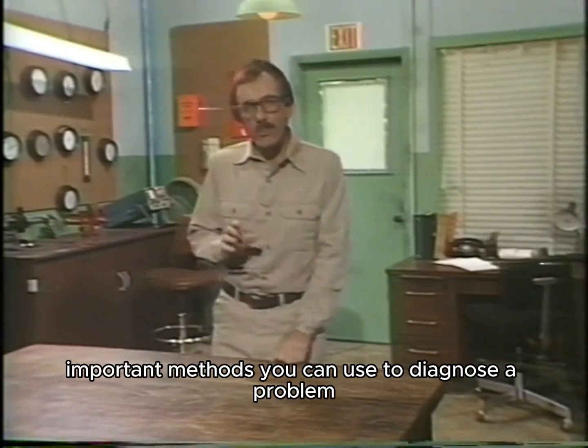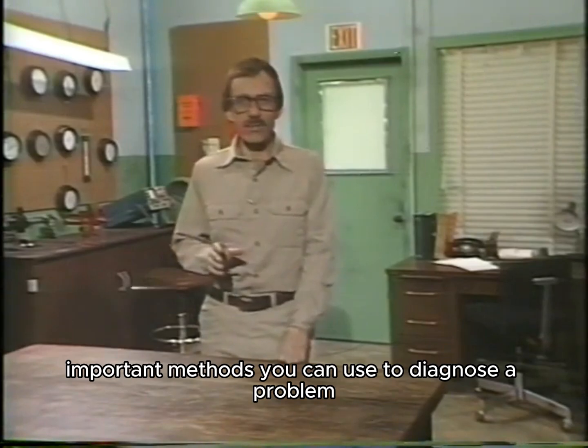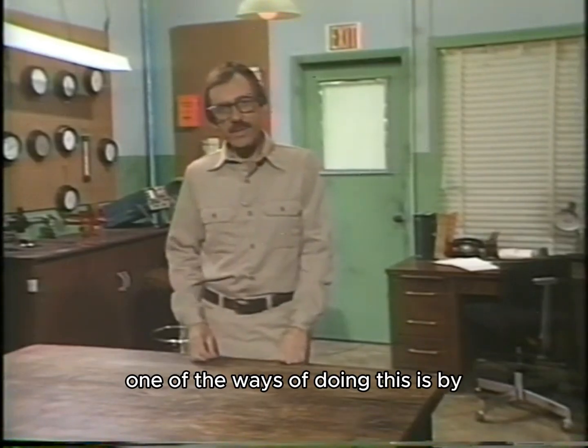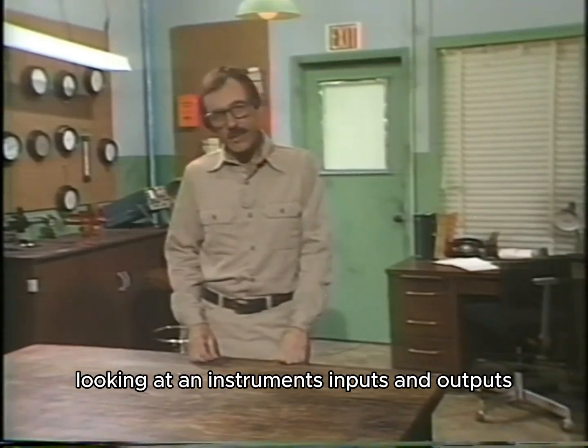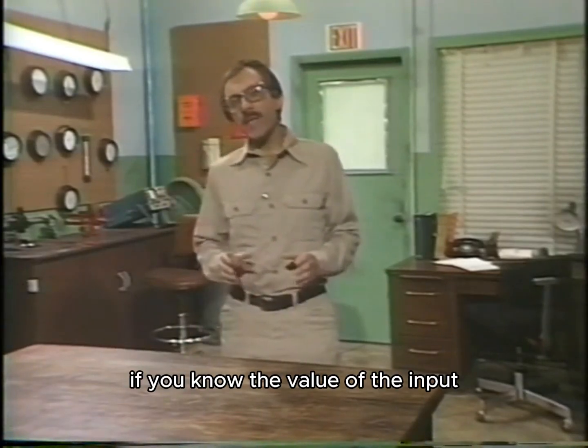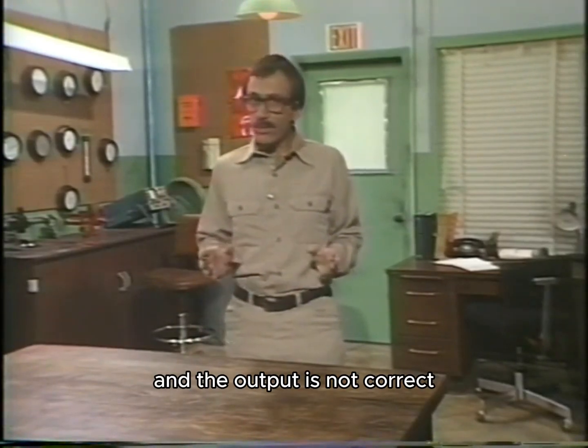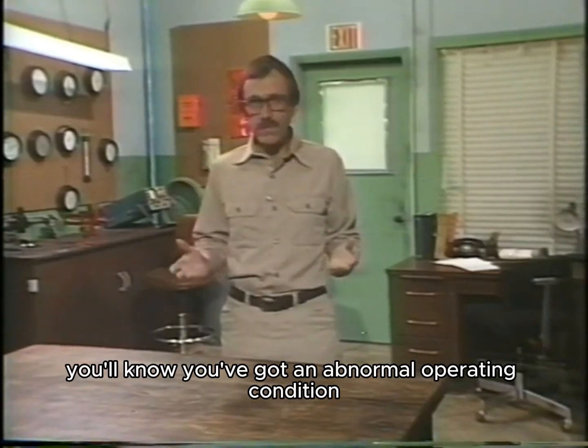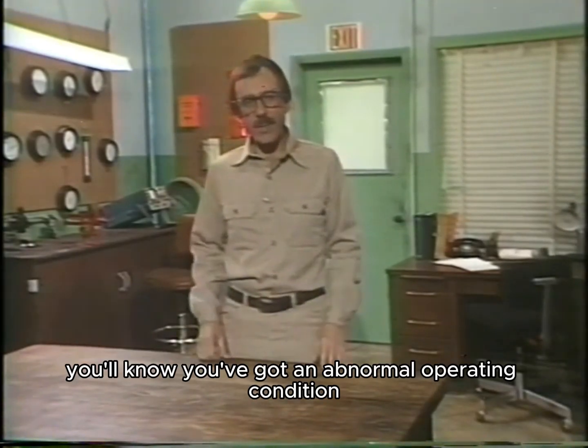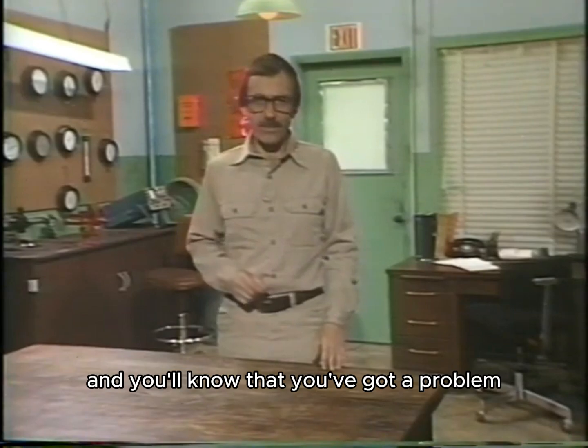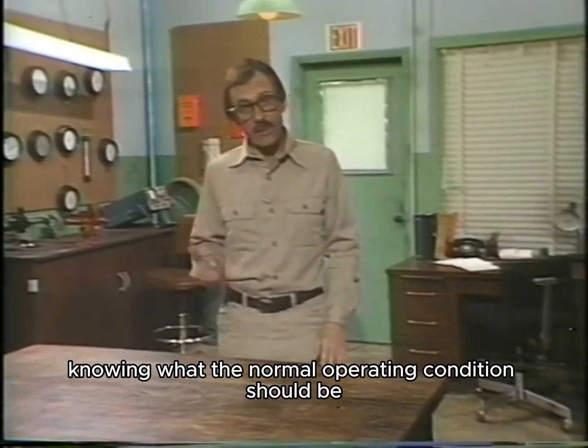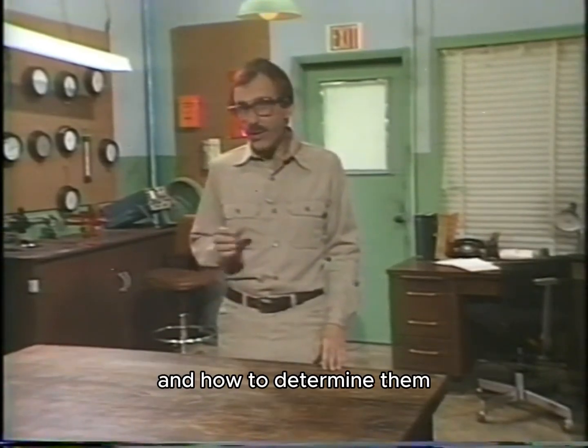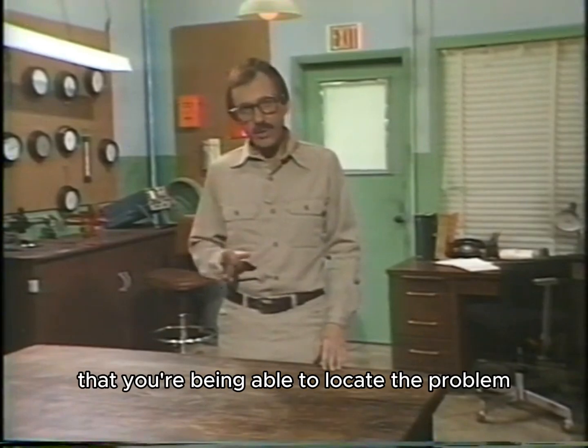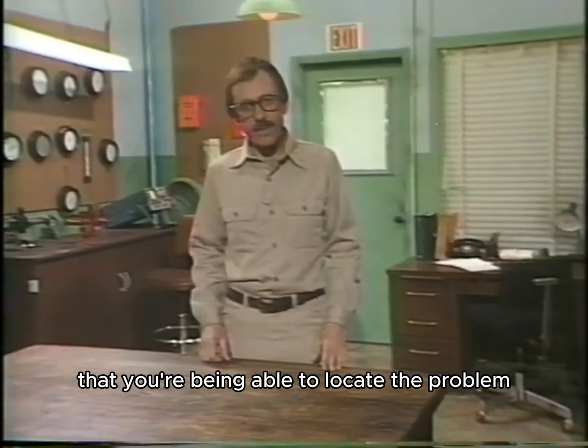There are several important methods you can use to diagnose a problem. One of the ways of doing this is by looking at an instrument's inputs and outputs. If you know the value of the input and the output is not correct, you'll know you've got an abnormal operating condition, and you'll know that you've got a problem. So knowing what the normal operating conditions should be and how to determine them can be critical to your being able to locate the problem.